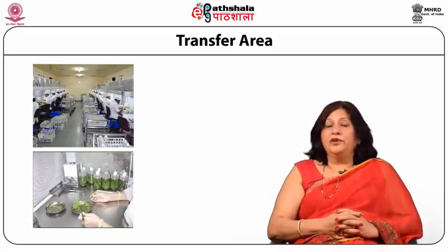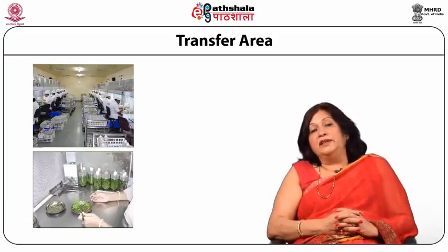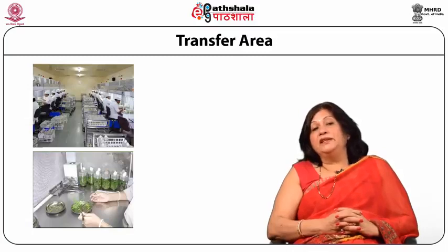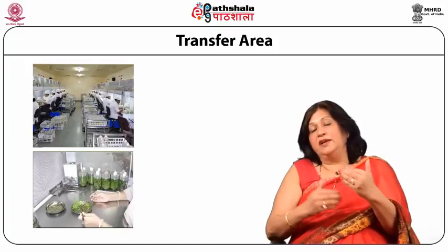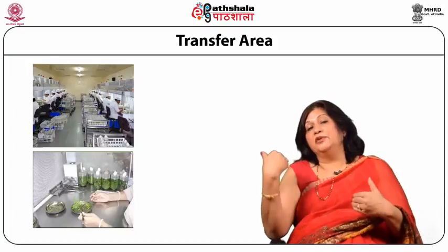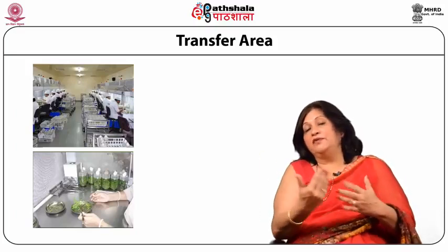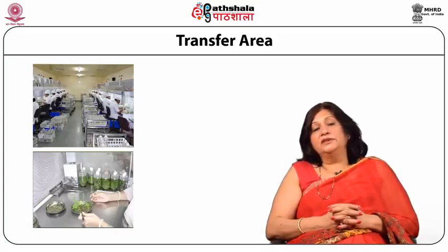Now, laminar airflow cabinets have unidirectional flow of air through HEPA filters. So HEPA filters prevent any microbes from getting into that particular area. And as I said, it's unidirectional. So it's coming from one side and the operator is sitting on the other. You open it on that side, so nothing goes from the other side and it's one-sided flow of air. And you'll find that all those who work in this area wear lab coats, which are again sterilized.